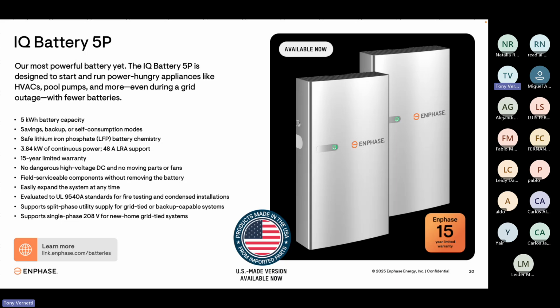And here you can see it has 48 amps of LRA support. That also increases when you add more batteries. So that's important for starting things like air conditioners or pumps that have motors — they demand a lot of electrical current when they first start. So the 5P battery is capable of starting those very powerful appliances and devices that have a high surge current.